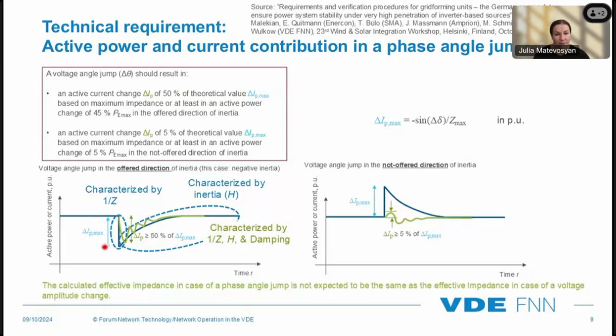But after that, there will be inertial response and damping. So this is the effect of this, what you can see in green. So this requirement is saying that from this maximum response that you can expect in the beginning, which is based on impedance, 50% of this theoretical response has to come from the resource that is providing this momentary reserve in the direction in which this reserve is provided. So basically, in this German market construct that is being proposed, the reserve can be provided either to positive phase jump or negative phase jump, or in both directions. So whoever is offering this service, they can choose.